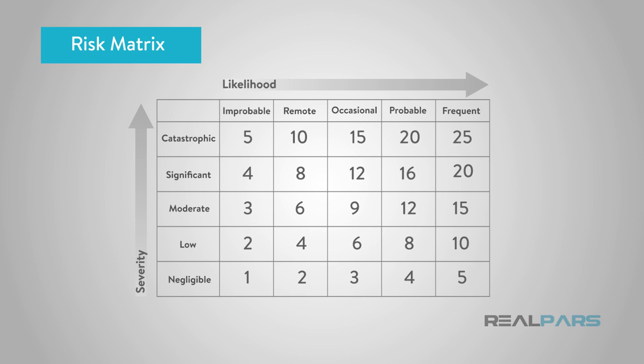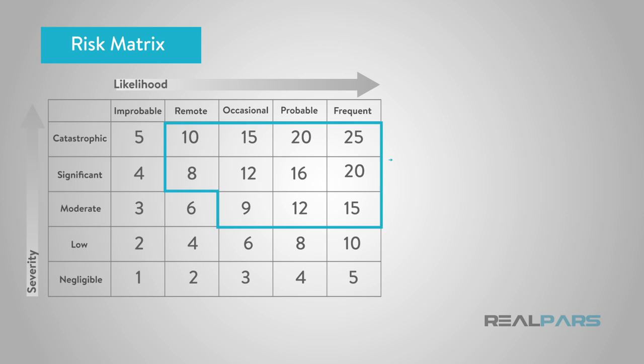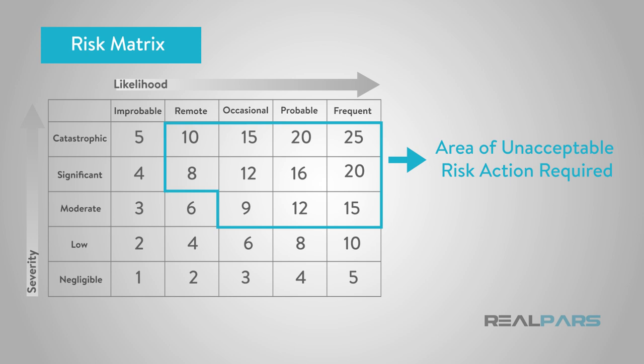In designing a safety instrumented system, the design team must do a detailed risk analysis, identifying all of the potential risks and deciding which require a Safety Instrumented Function to be defined. A detailed risk matrix can be used to identify the level of risk that is tolerable and at what point a function requires an SIF to be defined. This can be done qualitatively or quantitatively by assigning numerical values to the expected frequency and severity of the risk.